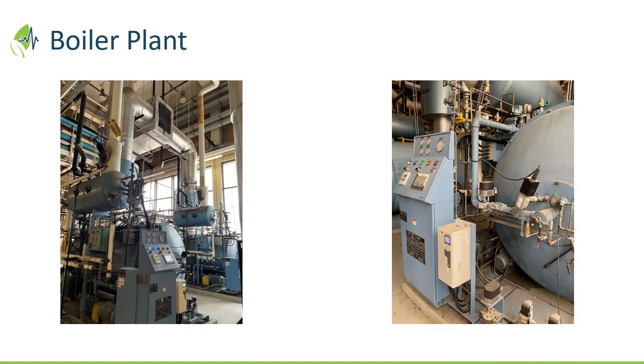Okay, good stuff. That shouldn't happen either if you have adequate combustion air in any room, which is governed by code. So unless someone starts blocking off air intakes because it's cold in the room, which happens all the time, it's very difficult to downdraft through an offline boiler. But it happens. Right. Paul, for a moment, talk to us about the economizer, and is that the draft damper above it?